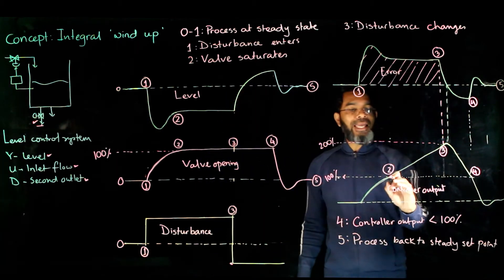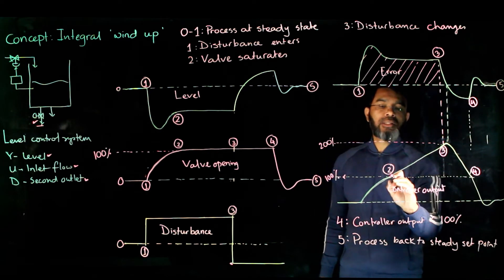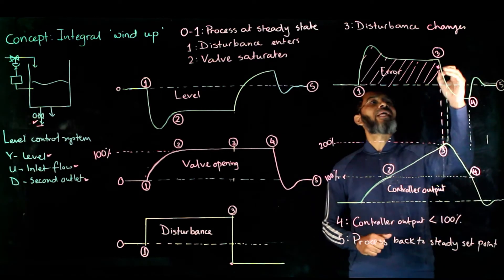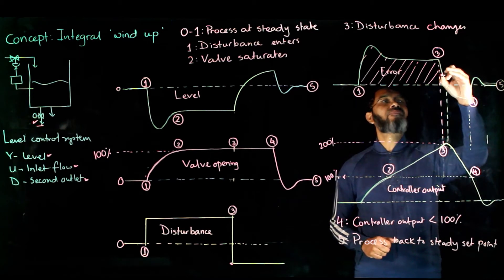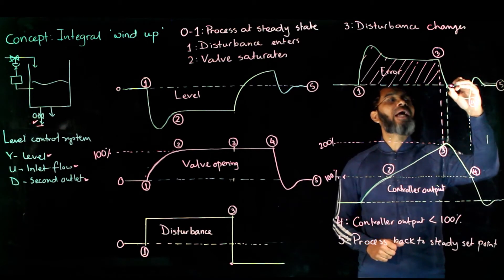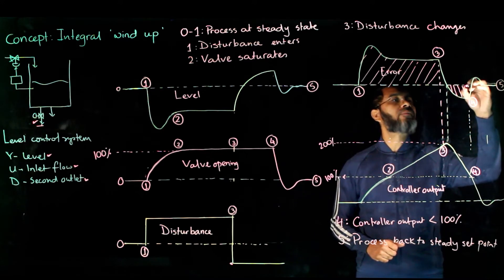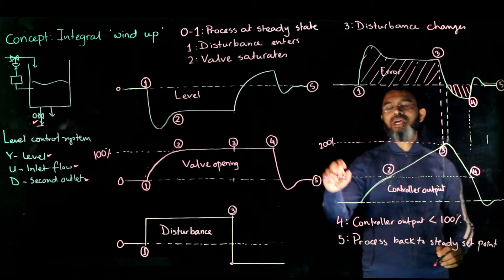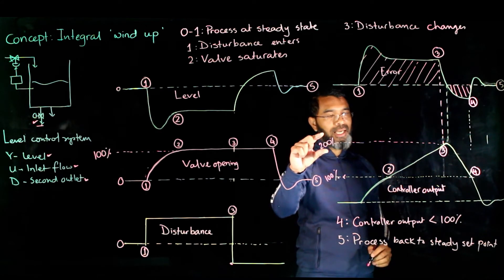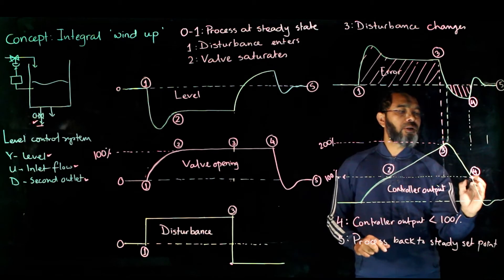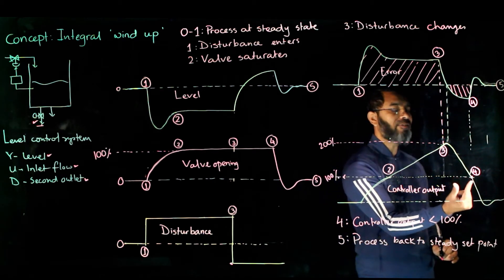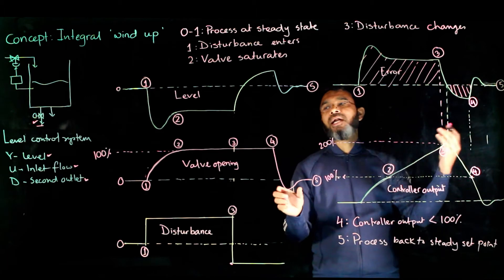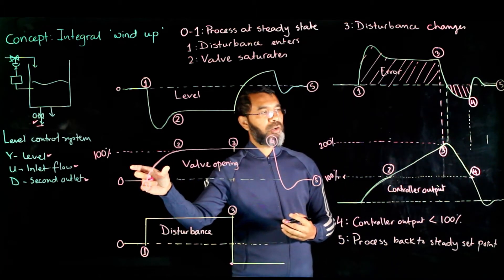Simply because, due to the integral action, the controller is calculating that the valve opening should be 200%. The error is now decreasing and becomes negative, but only when there is sufficient negative area does the control action start to change. Because the calculation was at 200%, it is not until the value comes back down to 100% that the controller output actually begins to decrease below 100%.